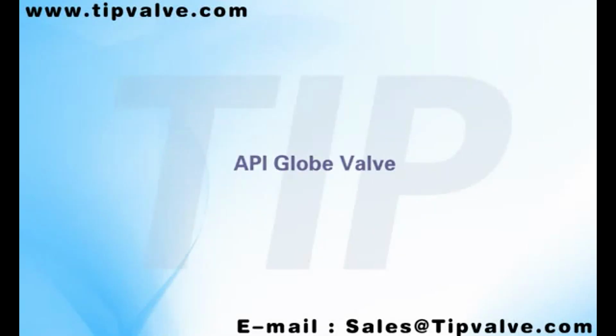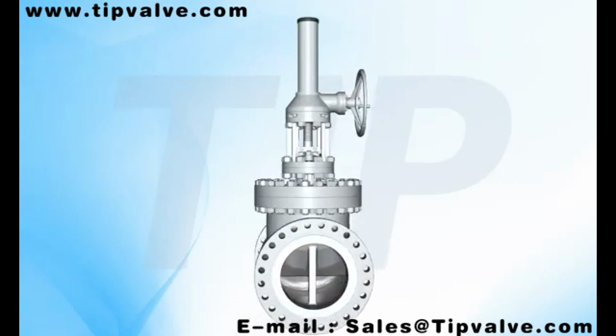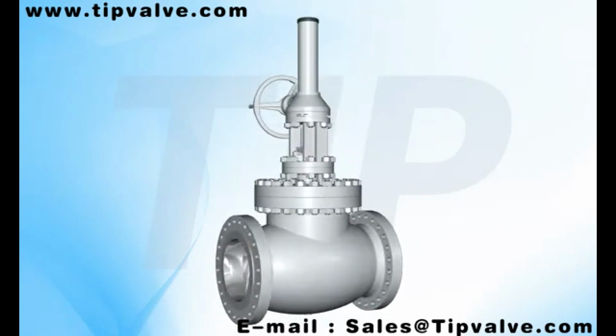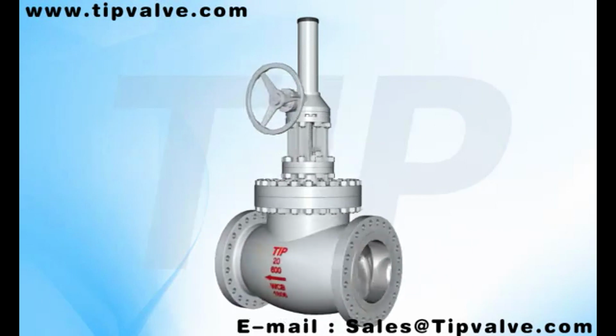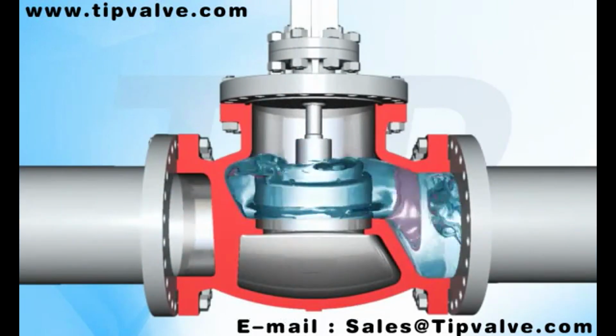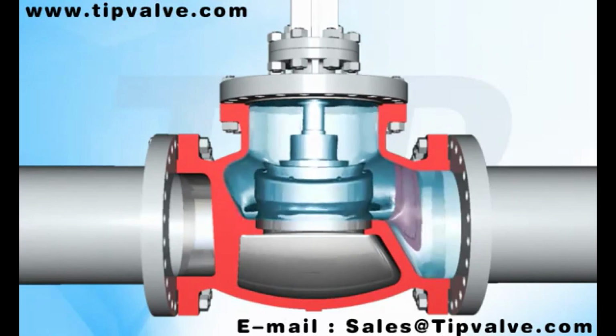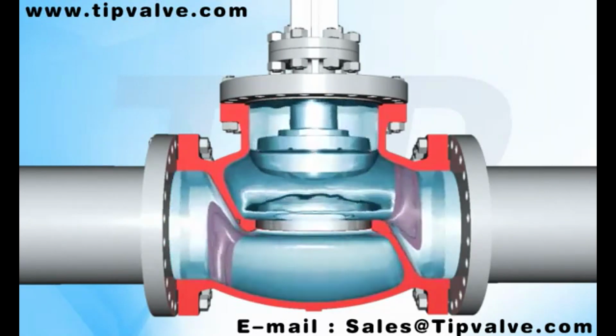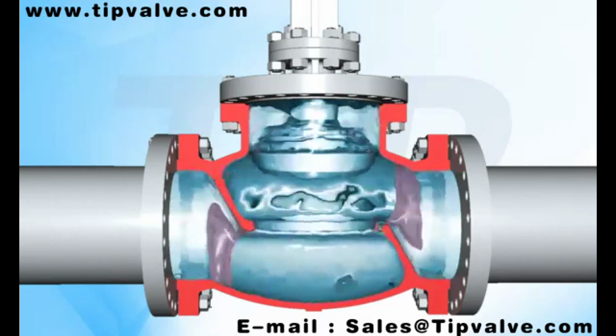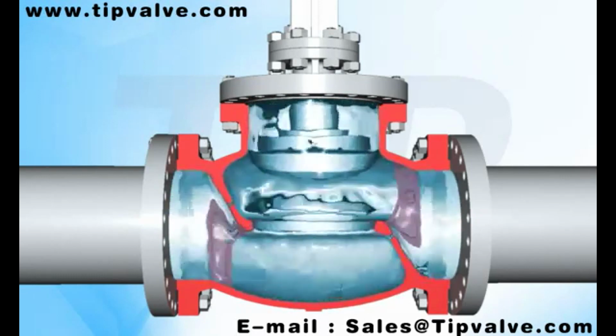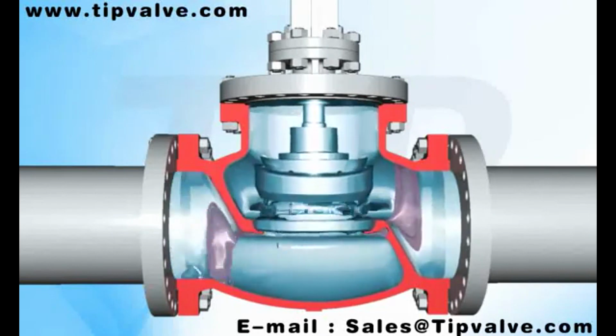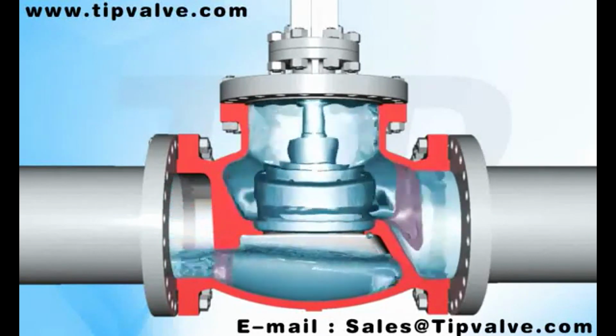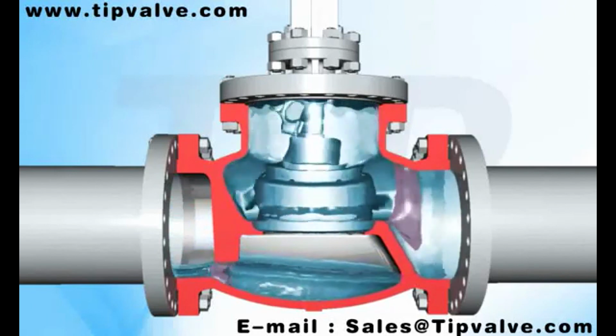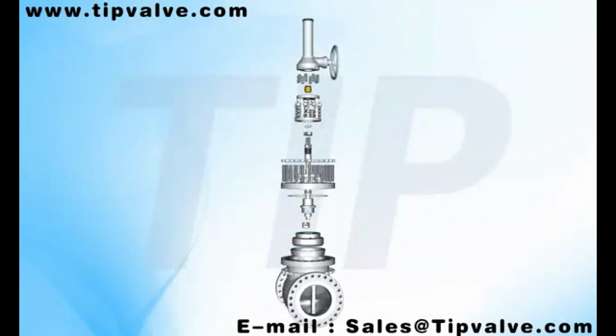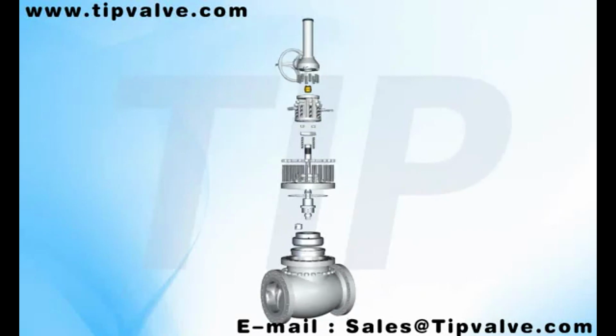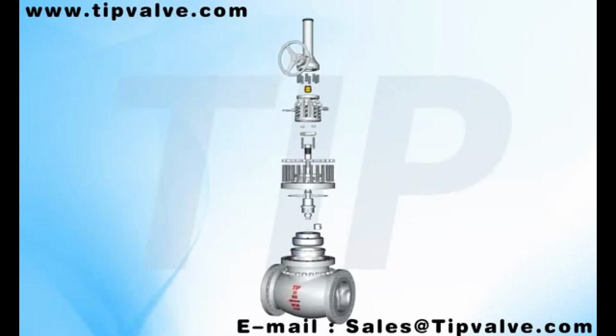Globe valve. Applicable standards. Pressure temperature class as per ASME B16.34. Design and manufacture as per BS 1873. Test as per API 598. Structure length as per ASME B16.10. Flange connection as per ASME B16.5, ASME B16.47, ASME B16.25. Sulfur resistance of material as per NACE MR0175.